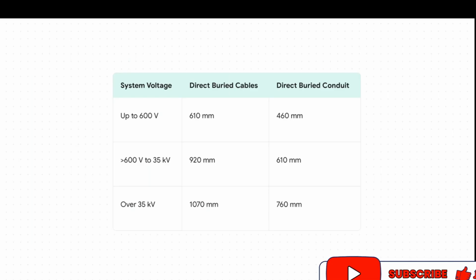And this table from the standard shows you just how specific it gets. Look at this. A medium voltage cable, say up to 35 kV, needs 920 millimeters of cover if it's direct buried. But if that same cable is inside a conduit, the requirement drops to 610 millimeters. These are hard numbers, you just have to know them.